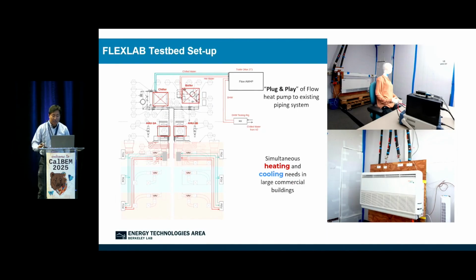As I just pointed out, for this demonstration of the CO2 heat pump at the FLEXLAB, the unique feature is the plug and play. We swap out the existing air-cooled chiller and natural gas boiler and keep using the existing hydronic systems to provide the cold water, hot water, as well as domestic hot water to this test bed. And just as I mentioned, it provides simultaneous heating, cooling, as well as hot water at the same time. It's just a matter of the building's load requirement.